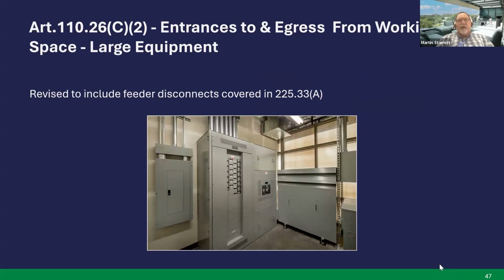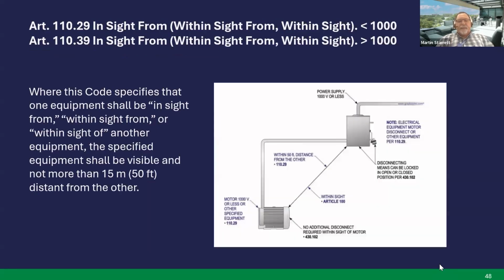26C2, entrances to and egress from working space, large equipment. The revision included feeder disconnects that are covered in Article 225.33A. So if you have a feeder disconnect that's over 6 foot, that's covered in that article, then you have to meet the entrance and egress working space requirements in this article. Next slide.